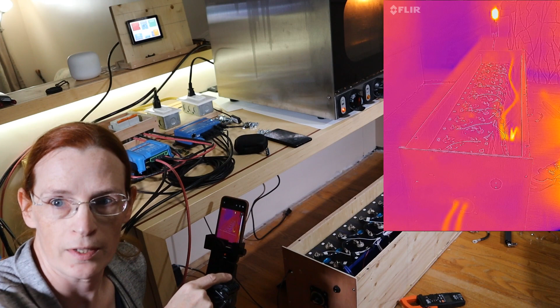One of the things I just noticed: if you recall, when I was first setting up to run the test with the rigid bus bars, I saw a couple hot spots. I don't see any specific hot spots with the flexible conductors. I was going to be happy if the flexible bus bars were about as good as the solid bus bars. I'm starting to think they might actually be better.